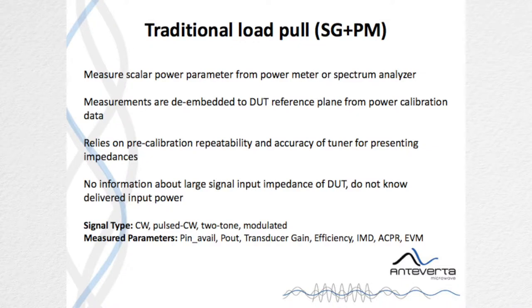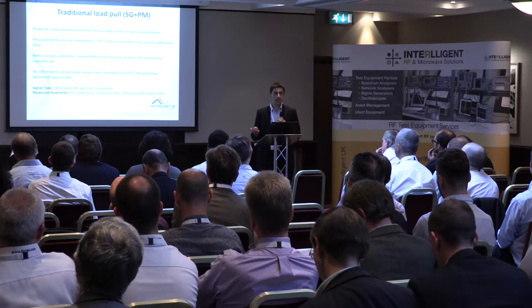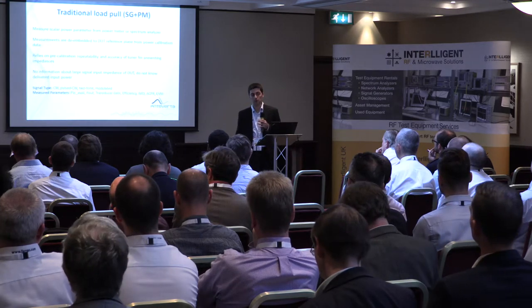There are a couple of problems with these types of systems, or drawbacks, let's call them drawbacks. Well, you can only measure scalar power. That means you don't have any information on your input gamma or on the input power delivered to your device. So you will know transducer gain, but you will not know power gain. One other potential issue is that the measurements are de-embedded to a DUT reference plane through a characterization of the tuner itself. So the accuracy of your measurement relies on the calibration accuracy of your tuner and on the repeatability of your tuner. So it's very important to have tuners that are reliable. In terms of the types of measurements you can do, you can essentially measure with all types of signals: CW, pulsed CW, two-tone, and modulated signals, but you have to be careful when using modulation up to the maximum bandwidth of your signal. I'll come back to that later.